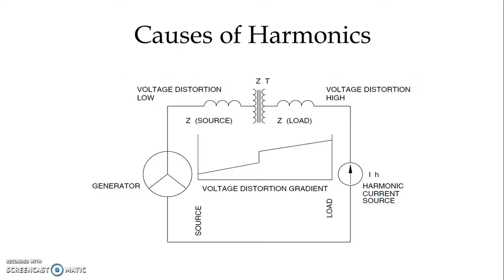From this figure we can see the voltage distortion gradient. On the source side, voltage distortion is very low. After the transformer, we have the load, and the harmonic current is generated from the load side and then propagates to the power system. So voltage distortion on the load side, because of current distortion being transformed into voltage distortion due to system impedance, results in very high voltage distortion on the load side.